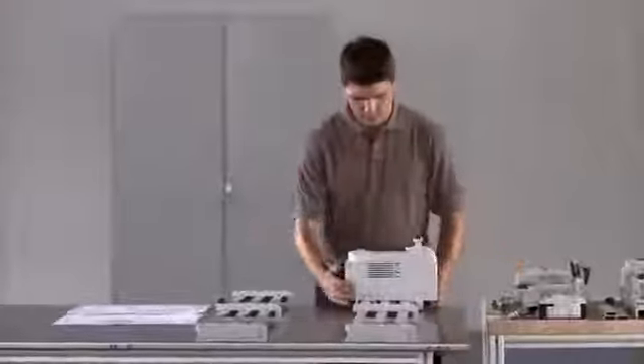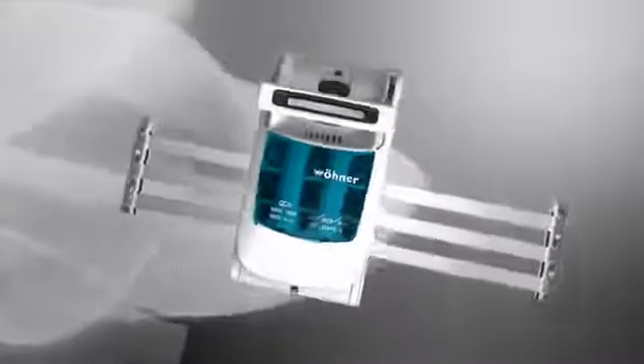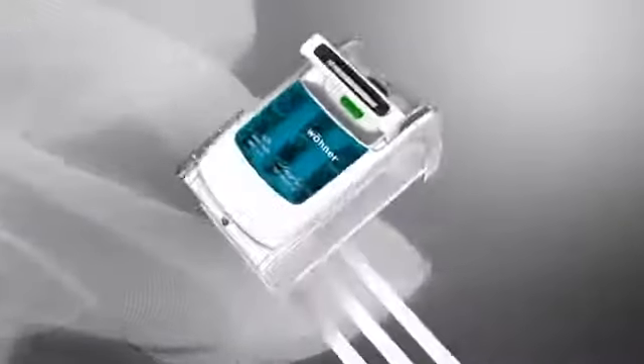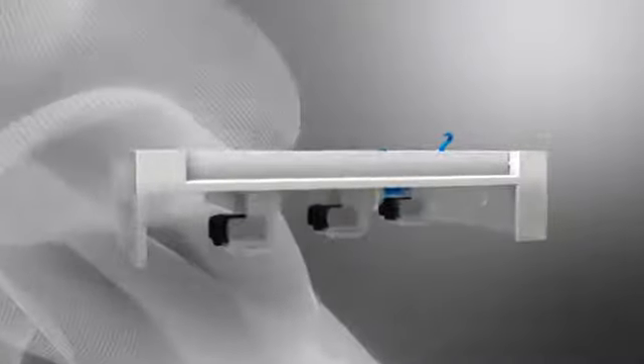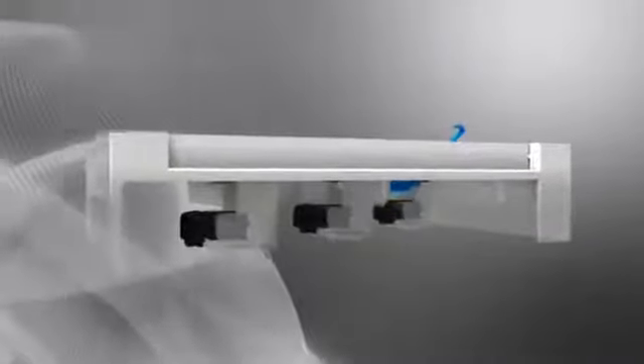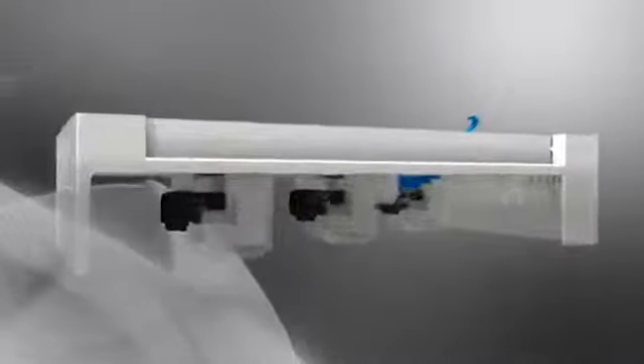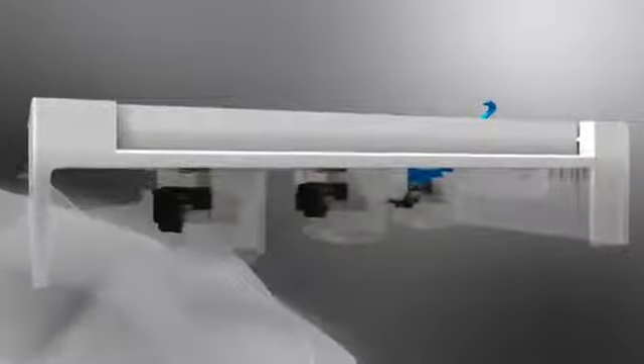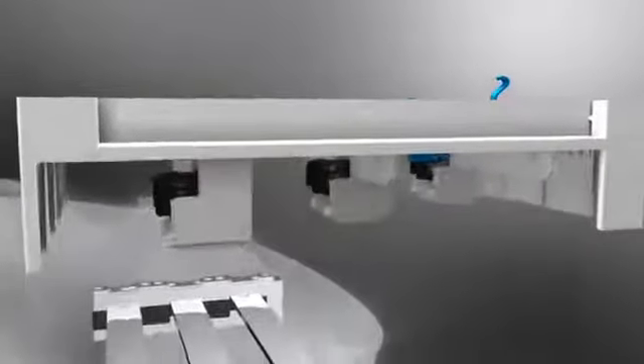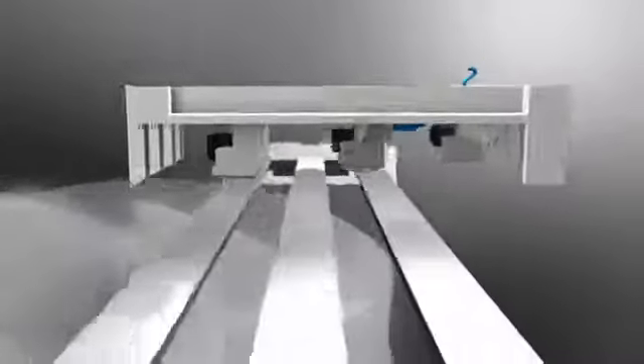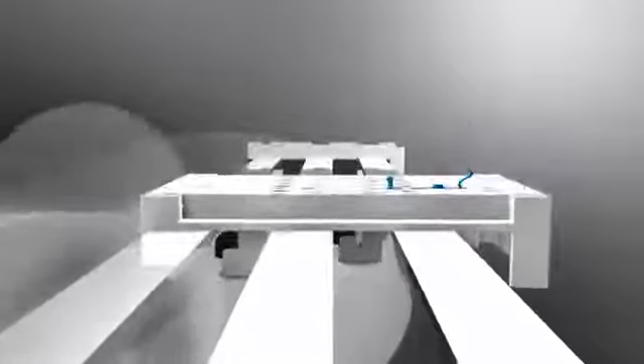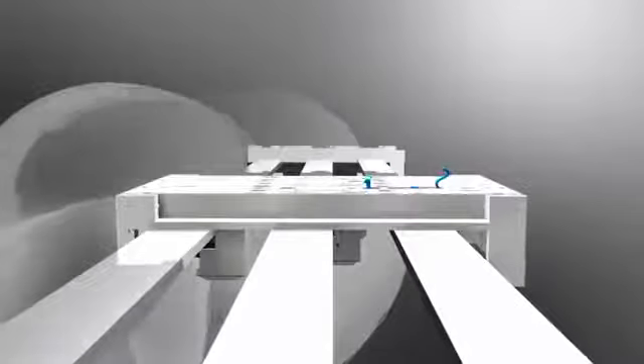Multi-pole system components can be snapped onto the 60mm bus bar system in one simple step and contacted without the need for any maintenance. All system components can be adjusted to 5 or 10 millimeter bus bars. Components with an insulated contact foot can be very easily adjusted to the respective bus bar thickness using a screwdriver. The module is placed on the 60mm bus bar system, engages, and is automatically fixed in the correct position.